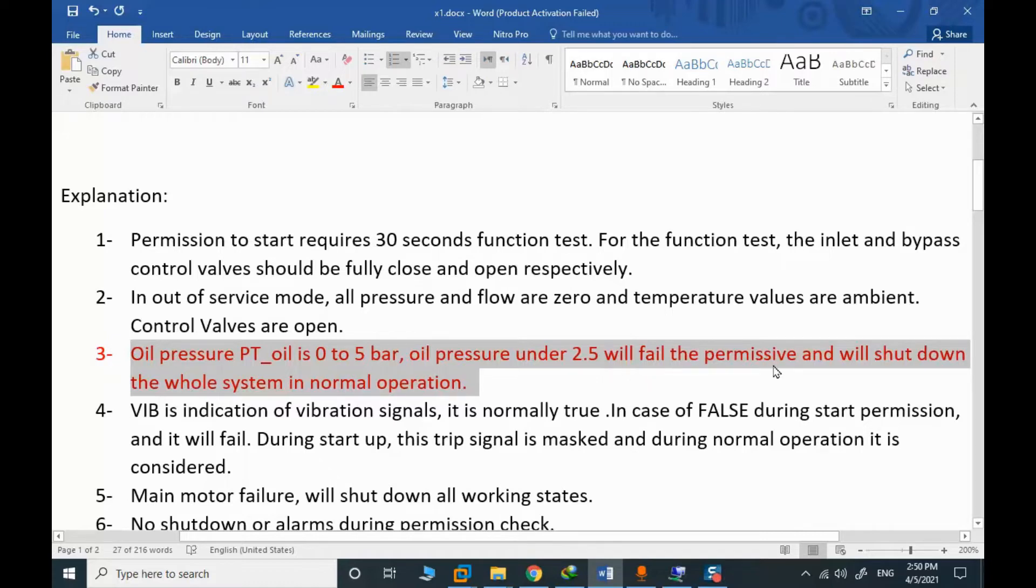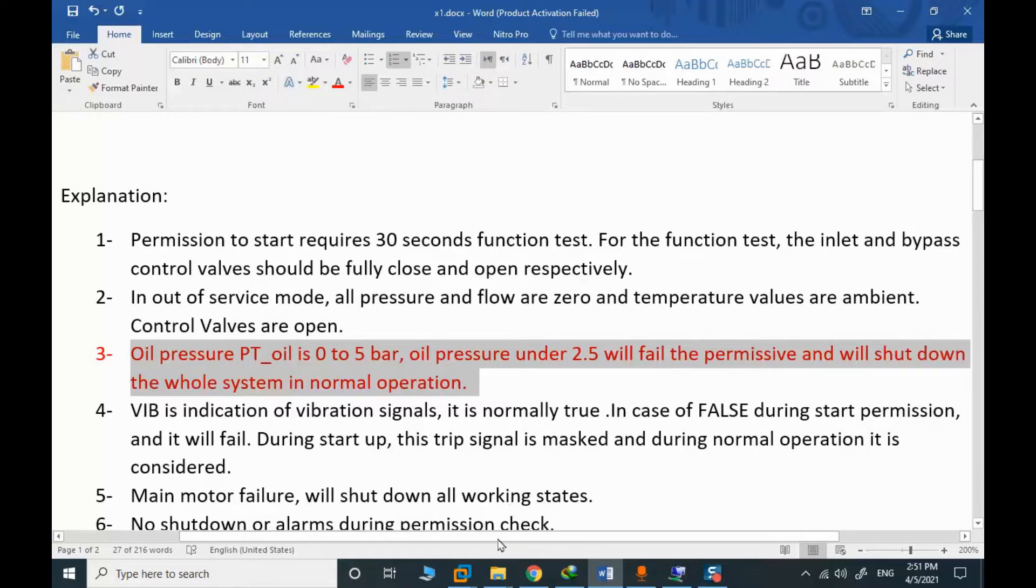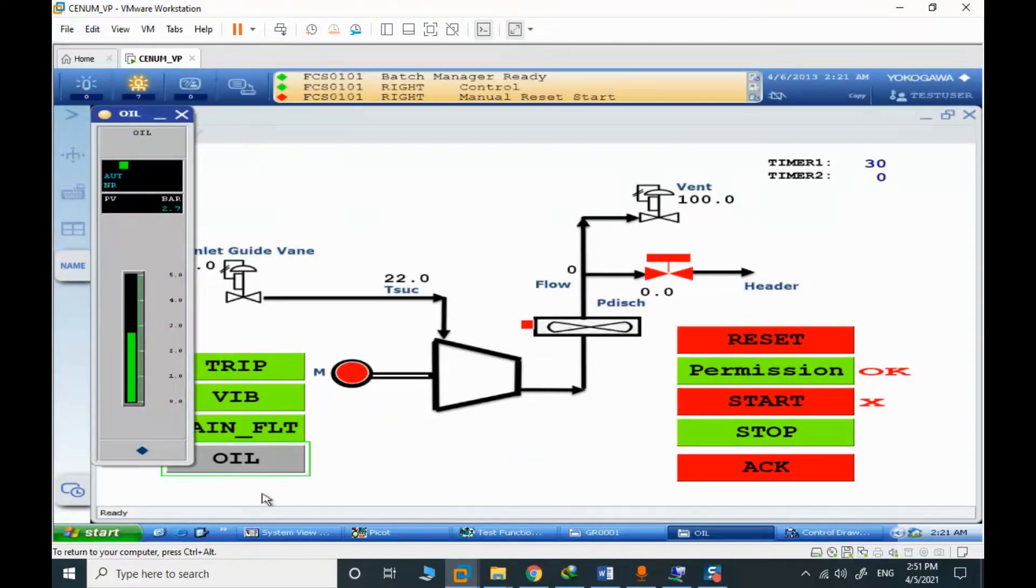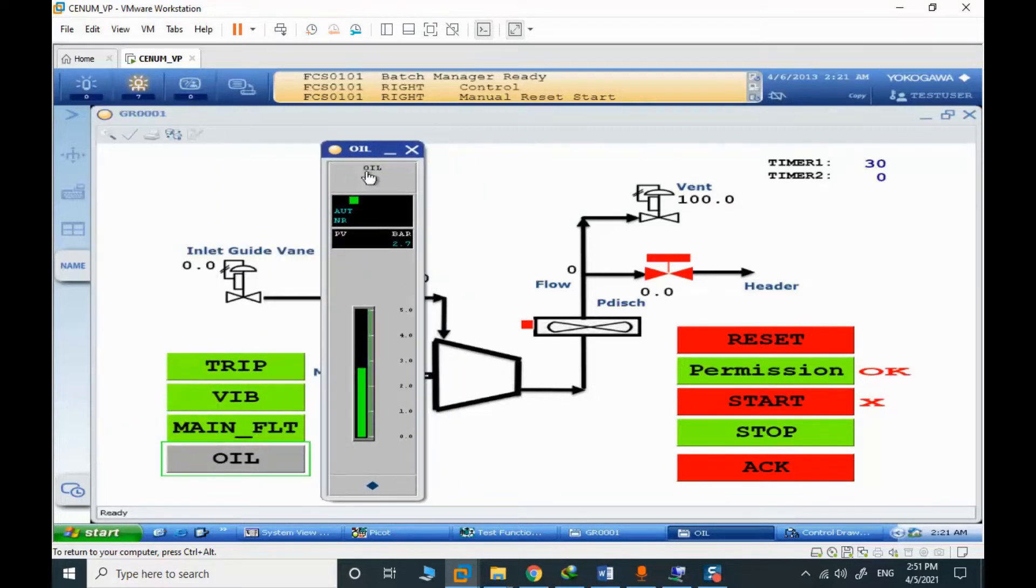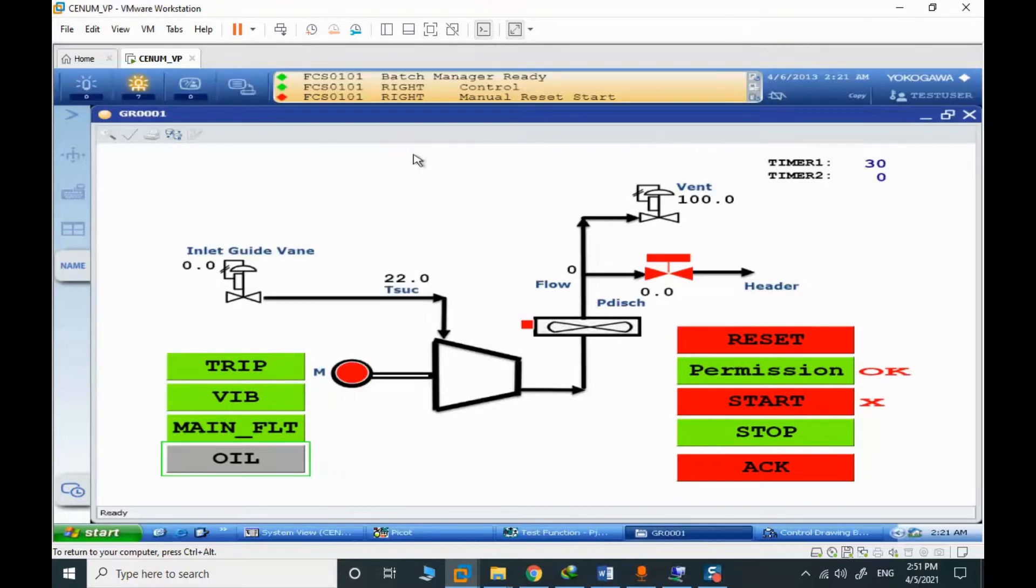Normally, even if we are in permissive in startup, when the oil pressure is getting low, we should shut down because it's abnormal behavior. The oil pressure is shown here. You can see that 2.7. Then we have the permission. The compressor will be lubricated with an electric oil pump.